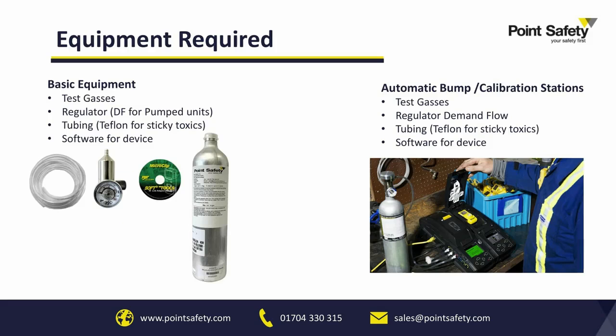So if you're looking at implementing a bump testing or calibration procedure, then there are two basic ways of doing it. For the most basic, you'll require test gases and a regulator, a fixed flow regulator, normally 0.3 to 0.5 liters per minute, for applying the gas to your monitor. You'll require tubing. And for some devices, many nowadays, you'll require the manufacturer software for that device in order to make any changes or to change the span of your detector.